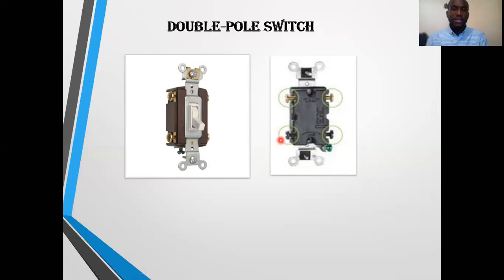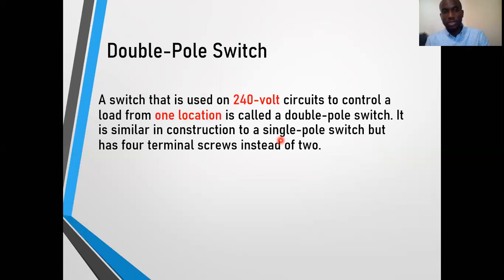Now we have to get into the principle of operation of the double-pole switch. A switch that is used in a 240-volt circuit to control a load from one location is called a double-pole switch. It is similar in construction to a single-pole switch but it has four terminal screws instead of two.